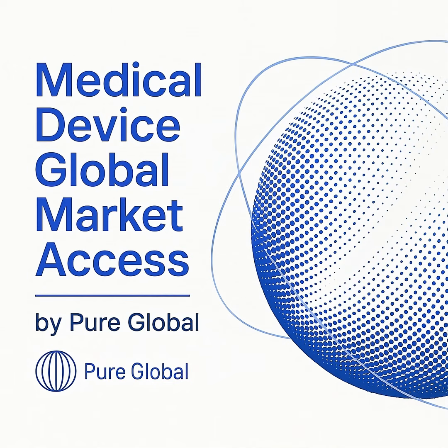So, what practical actions should regulatory and quality teams be considering right now? First, if your company is developing AI-based quantitative imaging software, you must immediately evaluate if it fits this new classification. Aligning with this pathway could significantly simplify your regulatory strategy and timeline. Second, begin developing a comprehensive PCCP framework. This is not just a submission document. It should be deeply integrated into your quality management system. Define your processes for managing, documenting, and validating algorithm changes according to the principles outlined in the FDA's final order.